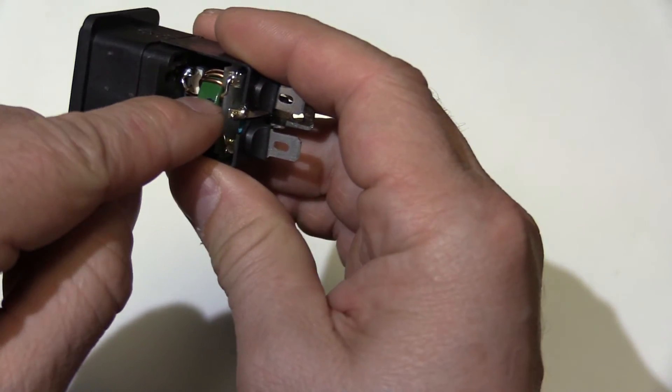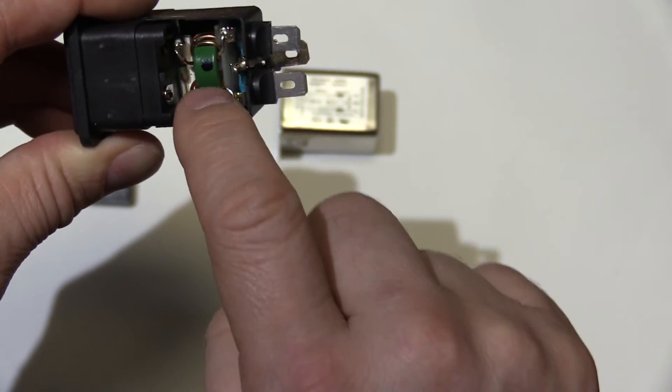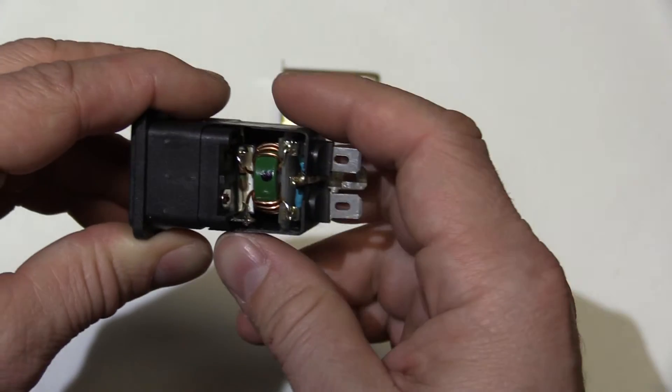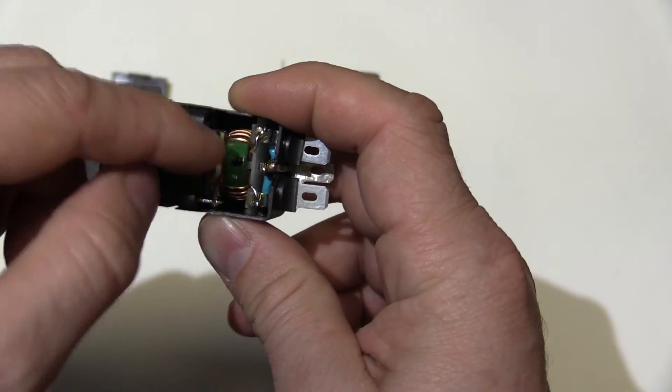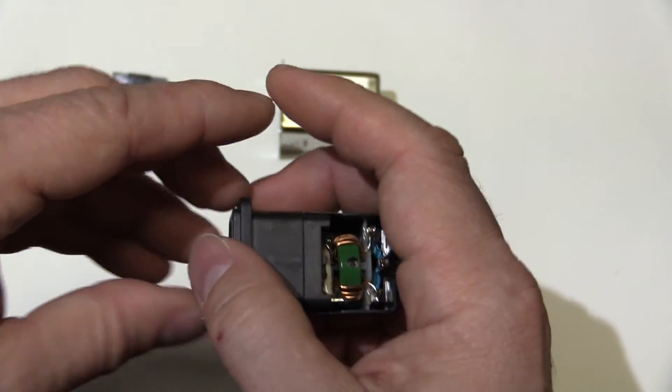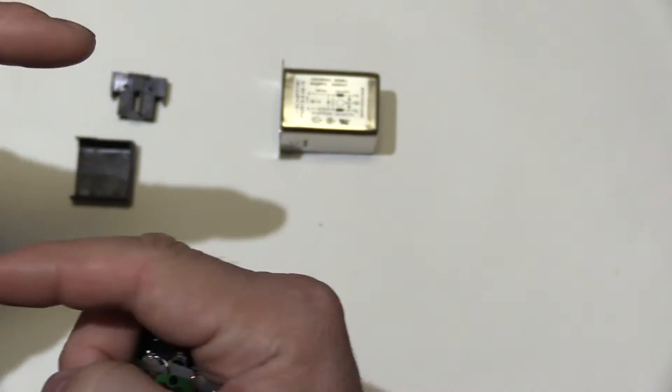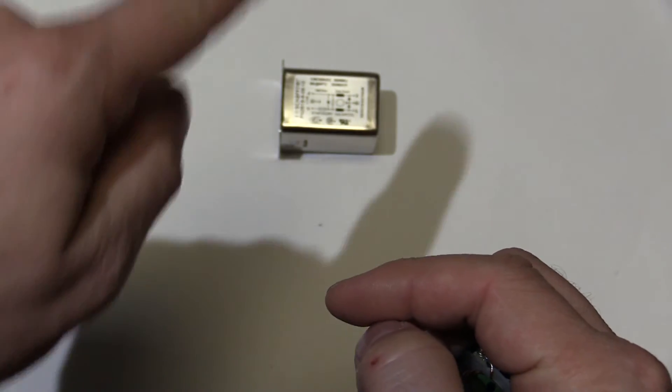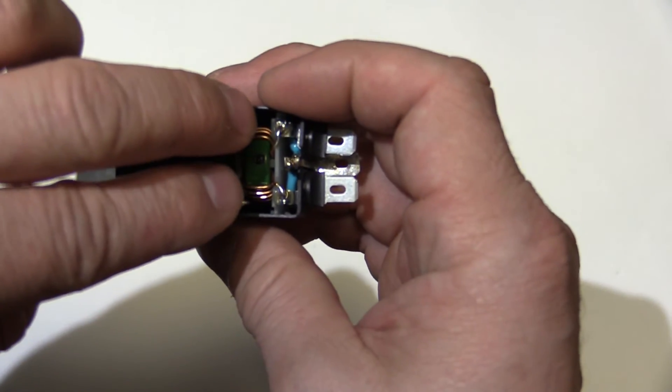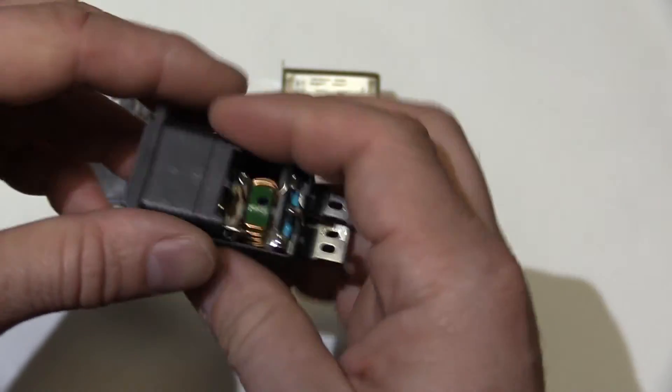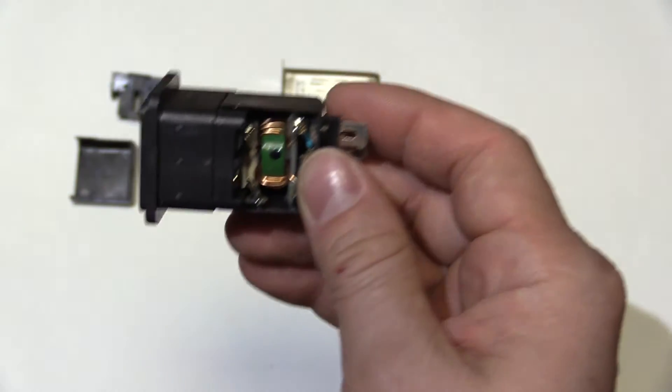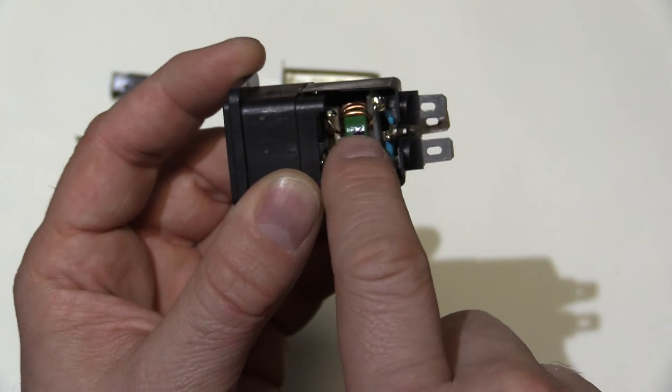This one is doing a similar job, but slightly different, where we've got two coils which are identical. So if there's what's called common mode interference, it'll cancel it out. Basically if you have your active and neutral, you imagine you've got your two wires like this, and there's a blip that comes on the line, and on the same line you get the same blip. As those two blips come through these coils, they cancel each other out, and on the other side you've got a nice clean signal, a nice clean sine wave. So that one there is getting rid of our common mode interference.